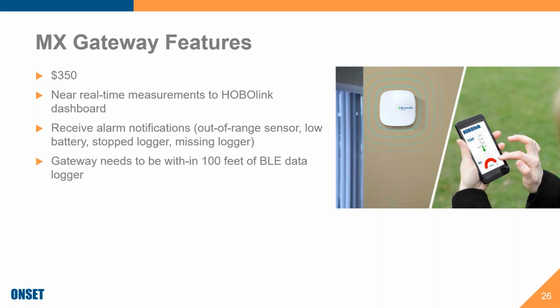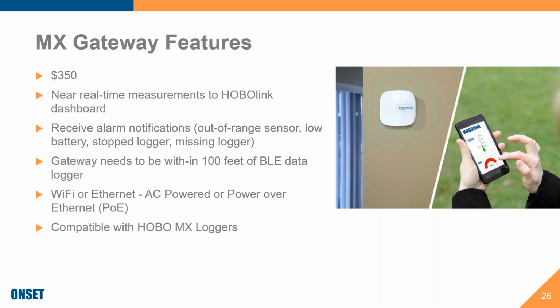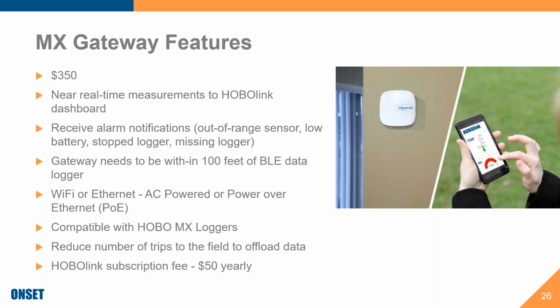Again, this is a star network, so all the Bluetooth loggers need to be within 100-foot range of the gateway. The gateway communicates to the internet through Wi-Fi or Ethernet. It's AC powered, so there's a wall wart it comes with, or you can use power over Ethernet. It's compatible with all the MX loggers, and again, it reduces the number of trips into the field. There is a HOBOlink subscription fee for the gateway, which is $50 a year.